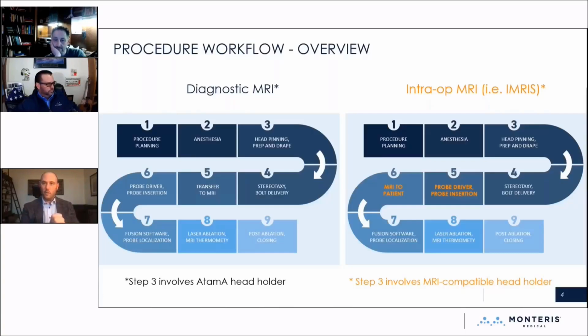That laser will go to a depth that you pre-prescribe with the Monteris folks, and then after that, you put your driver on, and once that driver is affixed, that's when you go ahead and roll the MRI out. So the big difference is, where do you stop the workflow? If you're doing a diagnostic scan, you do the surgical trajectory finding in the OR, and then you put the bolt in place down the same trajectory.